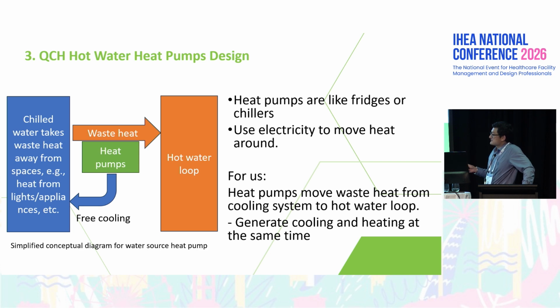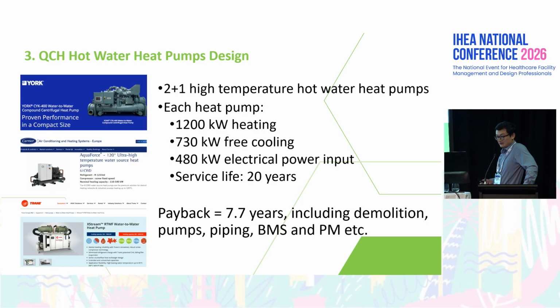This is a simplified conceptual diagram. We have chilled water loops that take waste heat from spaces, like waste heat from lighting, appliances, and even from people - 80 to 100 watts is how much power we generate, and different people may have slightly different metabolism, but that's the philosophy. We use heat pumps to move waste heat from the chilled water loop into the hot water loop. This way, we generate free cooling and produce hot water at the same time. That's the way we'd like to go.